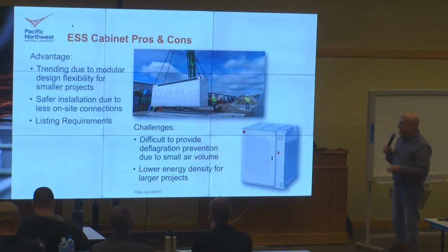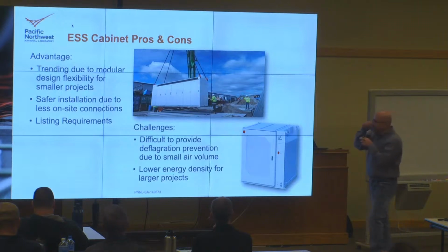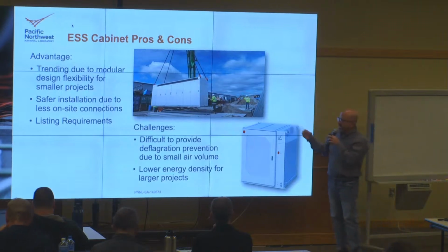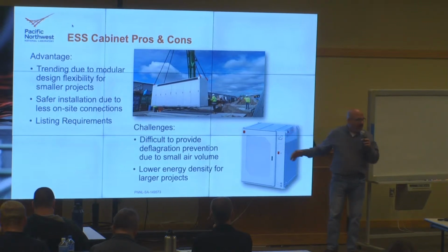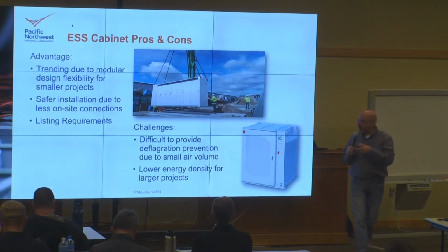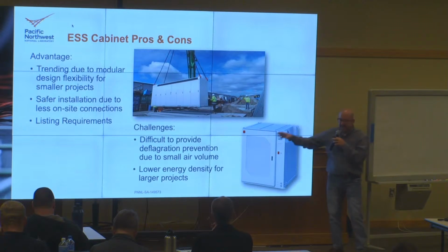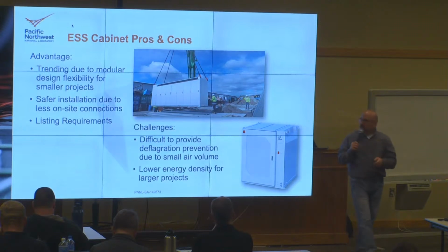Okay, so the cabinets. Why is the industry moving to cabinets? More modular designs. It's safer to install because the batteries are very often preloaded in it at the factory, and they can get that widget listed. All of them are kind of the same; you're just building your plant off of hundreds of these. But the challenge is, again, a lot less air volume inside there to exhaust.